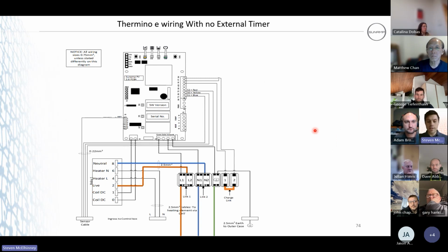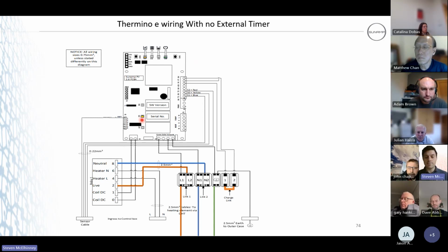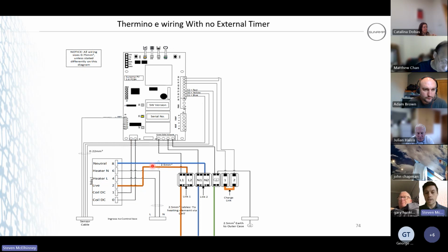So, Thermino E with no external timer fitted, what's going to happen? You've got your lighting sequence here, you've got your power LED, you've turned it on for the first time, and your element LED is now active. What you'll see with that is LED D5 on the PCB illuminated. That's telling us that the battery is detecting a demand. So it will then energize the coil of the relay. This is a DC relay, so that's going to be 12 volts DC coming from this point. That'll close the relay, which will then send power to the element. Looking back, that permanent live going to that relay, as soon as we close that relay, it sends power. And then if we get up to temperature, we break it, and your LED D5 will go off as well.